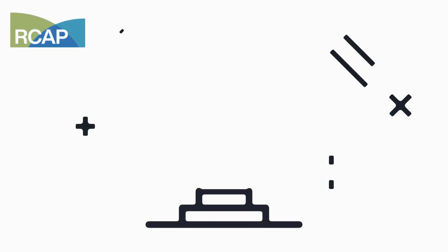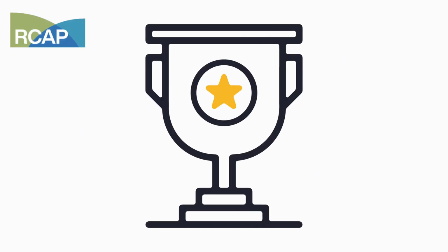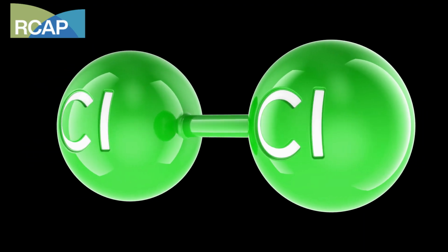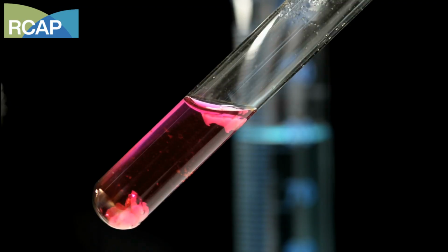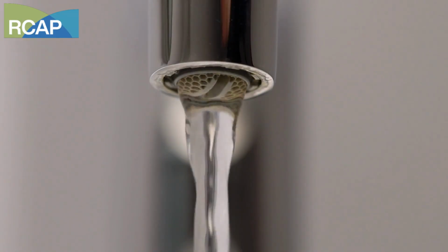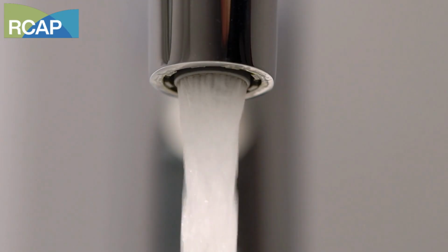There are several advantages for the use of chlorine as a disinfectant. One of the most significant advantages of using chlorine in one of these forms is that it leaves a residual of the chlorine disinfectant in the water distribution system. This will help to keep your drinking water safe from the water treatment plant to the customer's tap.